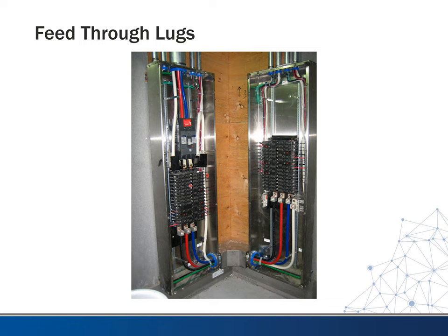So code-wise, this is really all one panel. This main breaker here is protecting all of these breakers. And you can see the busing and the feeders are all sized the same for the same amperage of the breaker. So you're just getting more branch circuit breaker space by doing this.